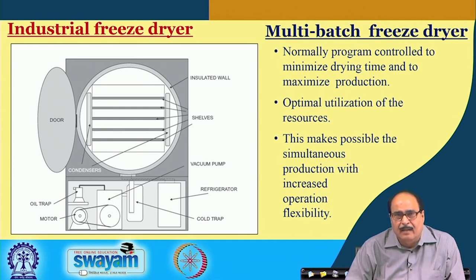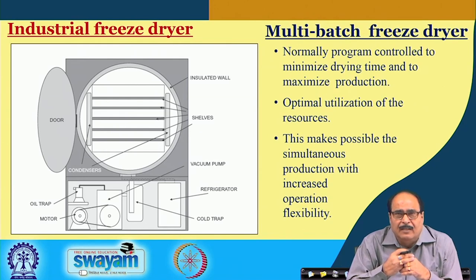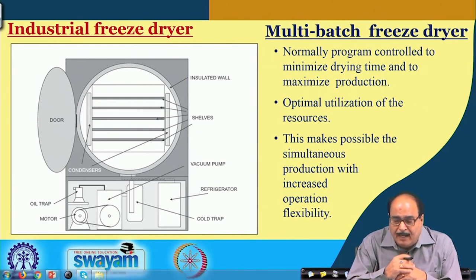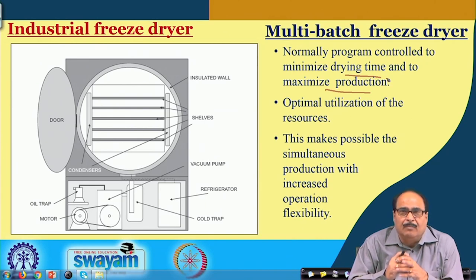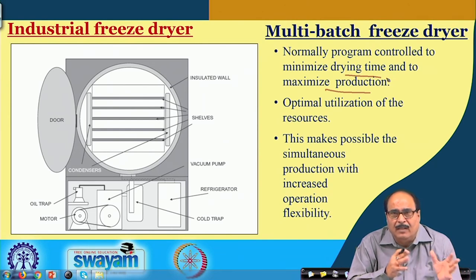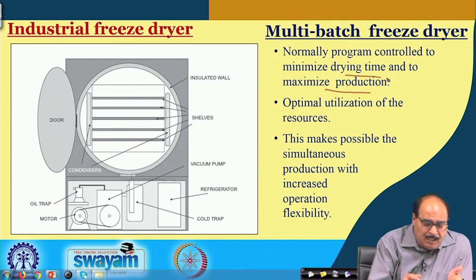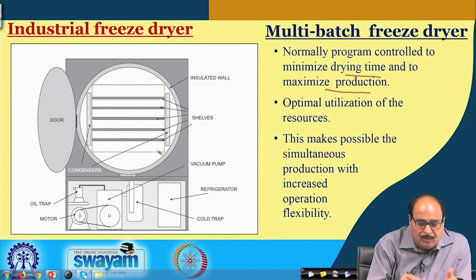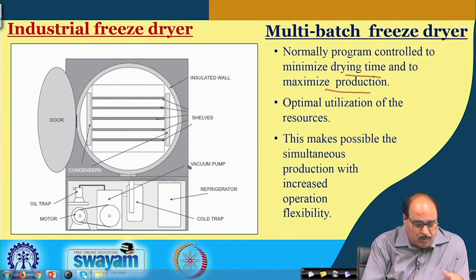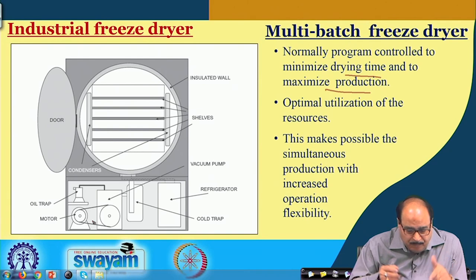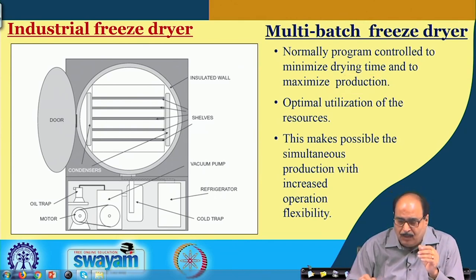Industrial freeze dryers may be of the multi-batch type, as seen in the first slide. These are normally programmed to minimize drying time and to maximize production, resulting in optimal utilization of resources and making possible simultaneous production with increased operational flexibility. The chamber has condensers and insulated walls to avoid heat loss. The shelves hold the product, and the system is provided with a vacuum pump, refrigeration for freezing, cold traps, and necessary instrumentation.